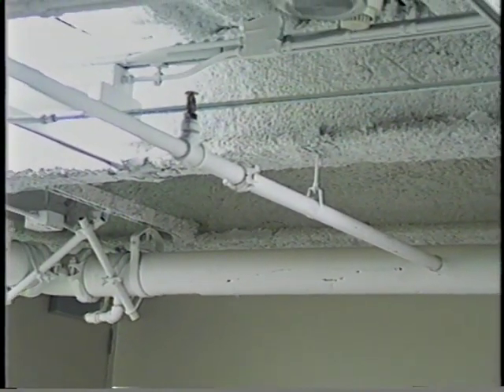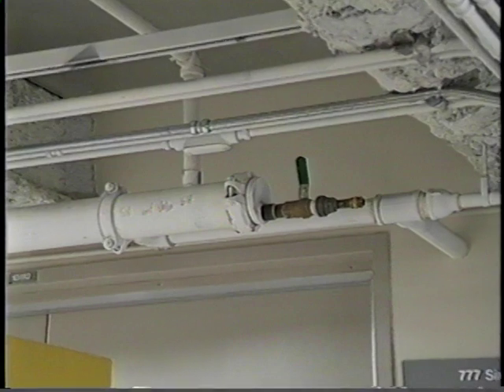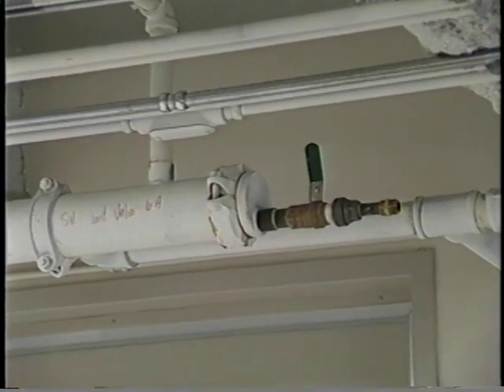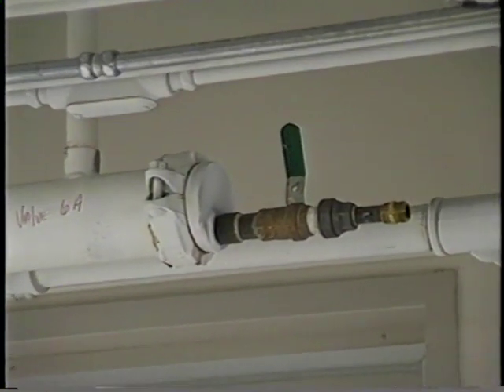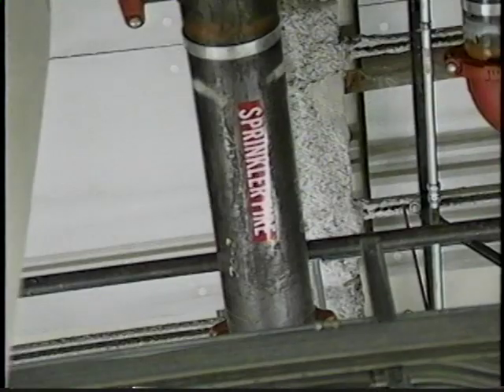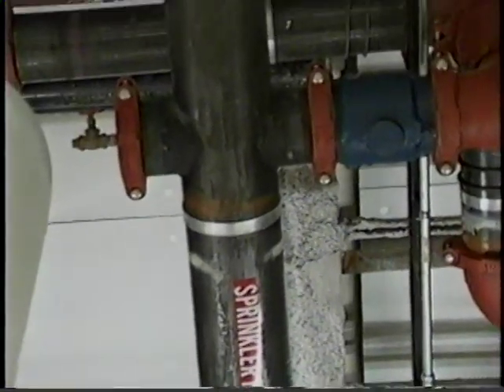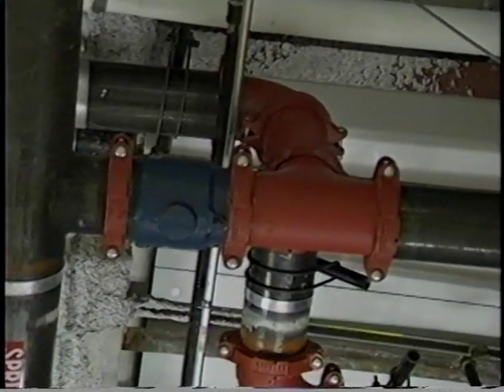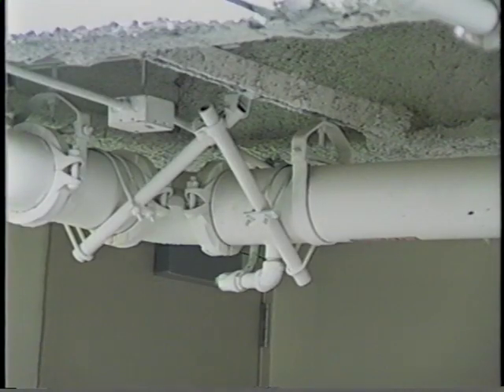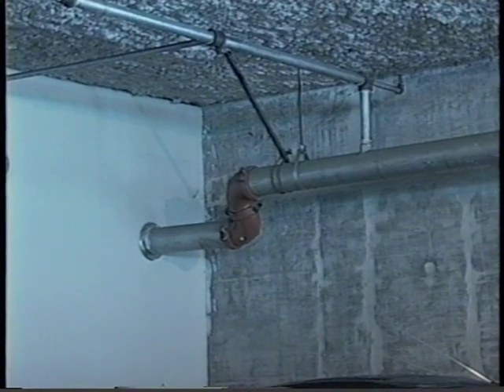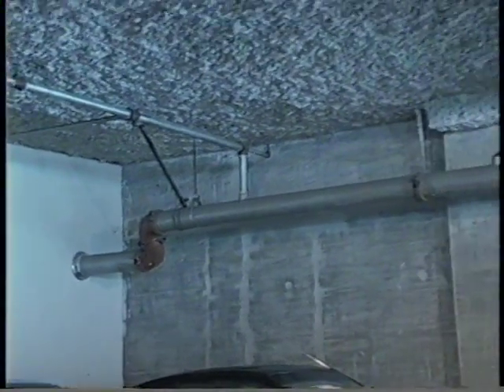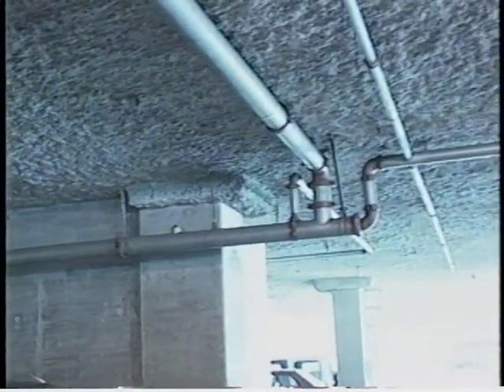Cross mains extend past the last branch lines and are capped to facilitate flushing. System piping decreases in size from the riser outward. The entire system is supported by hangers and clamps. All pipes in a dry system are pitched to help drain the system back toward the main drain.